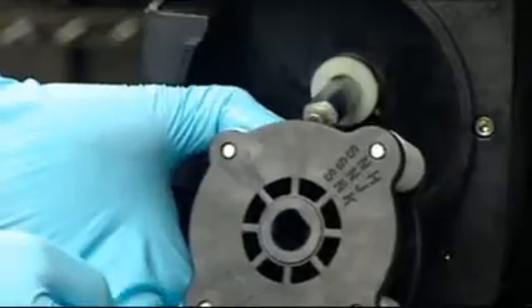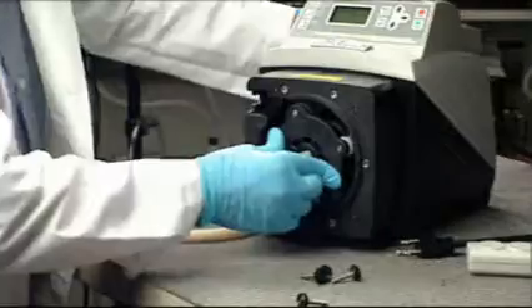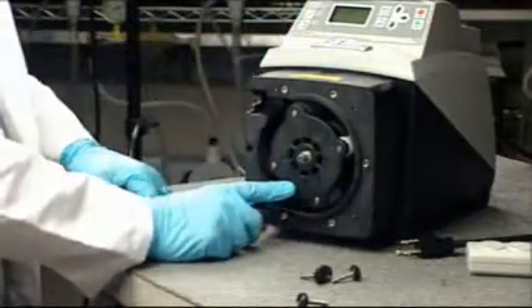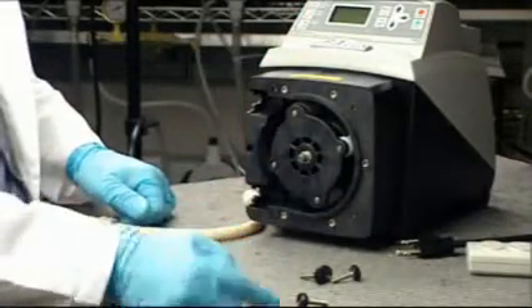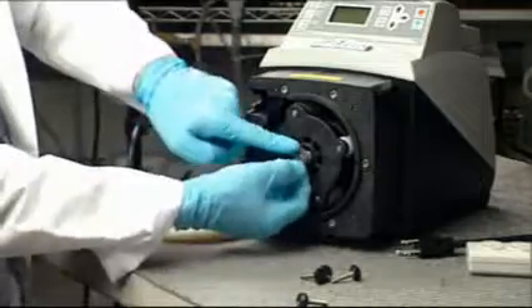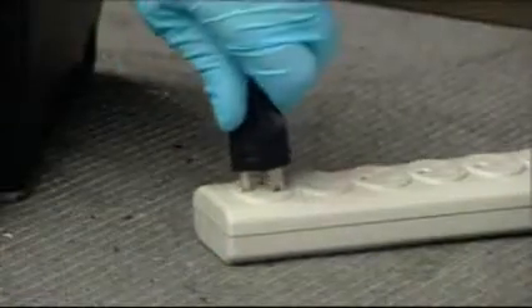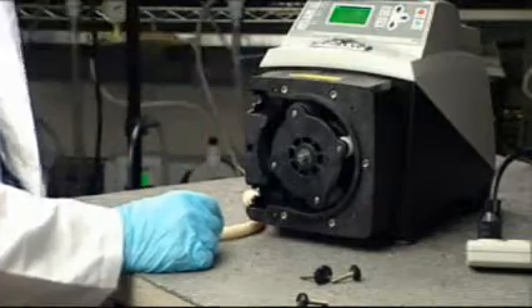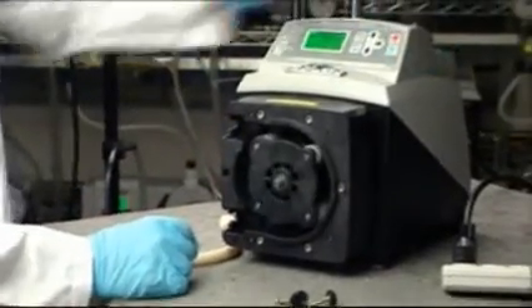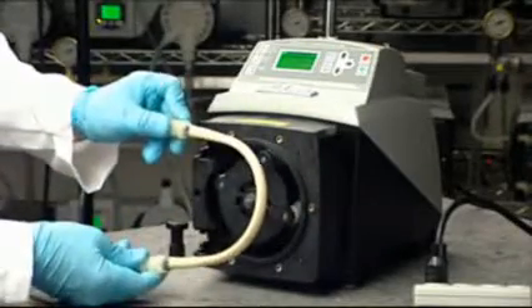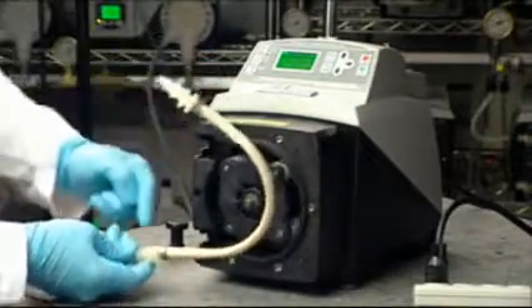With the front side facing forward, replace the roller assembly by sliding the assembly onto the motor shaft. Replace the small spacer washer onto the motor shaft. Apply power to the pump. Press the start button. Notice that the roller will only rotate at a slow, safe speed. Notice that the pump tube is curved.